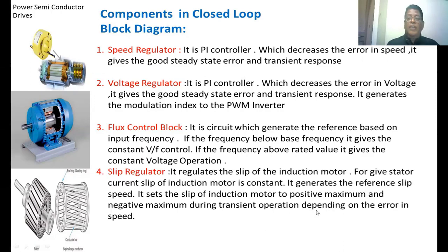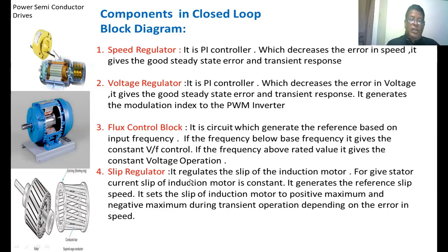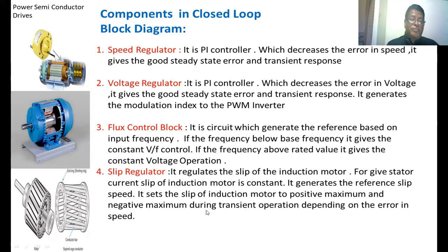Slip regulator: Slip is the difference between the synchronous speed of a motor and the actual speed of the motor. The slip of the induction motor highly depends on how much current is taken by the induction motor. It regulates the slip of the induction motor. For a given stator current, the slip of the induction motor is constant. It generates a reference slip speed, and sets the slip to the positive maximum value or negative maximum value during transient operation depending upon the error in speed.